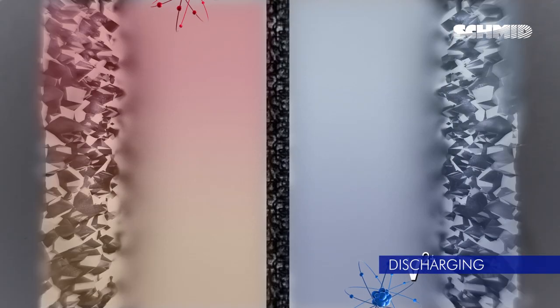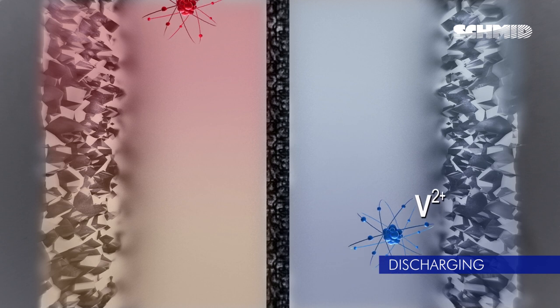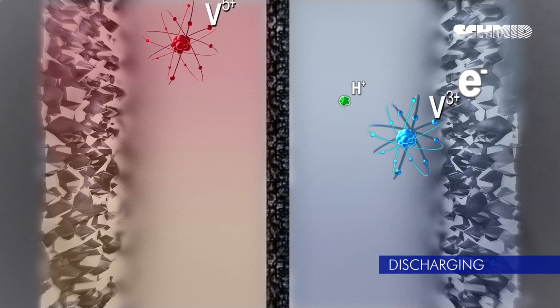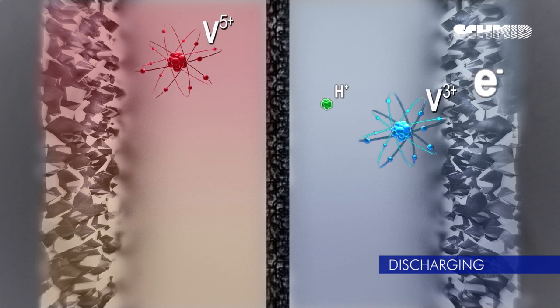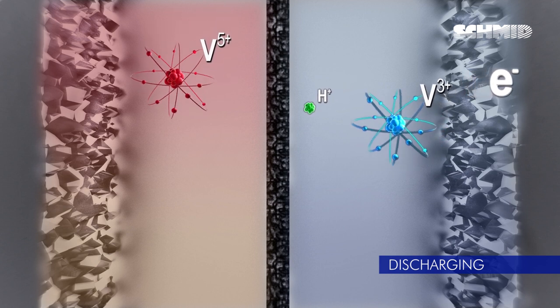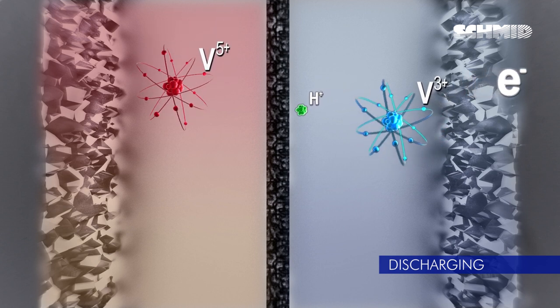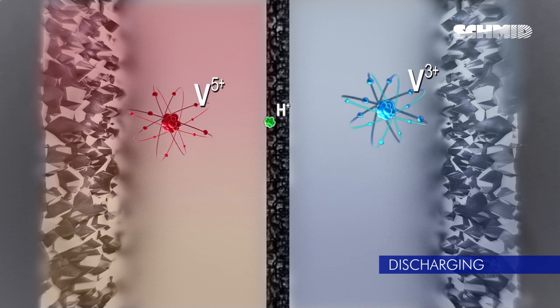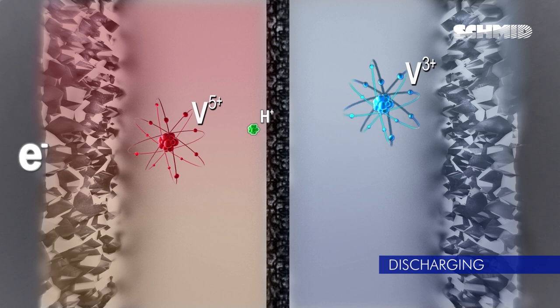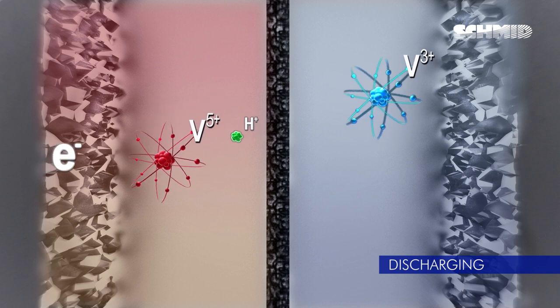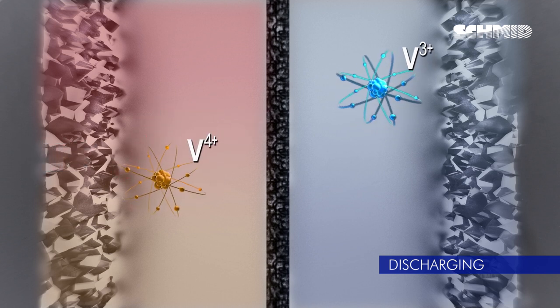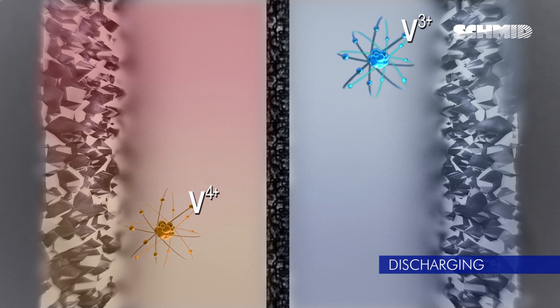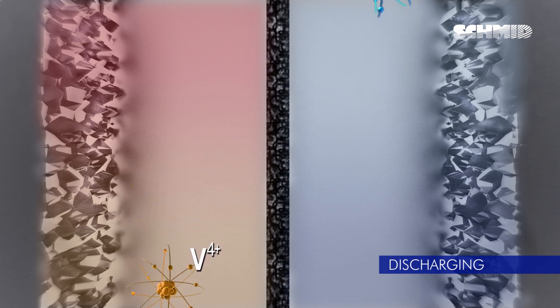At the molecular level, the reverse of the charging reaction occurs. Vanadium 2 is oxidized to form vanadium 3, releasing an electron which carries the electrical energy. For charge balancing, a hydronium ion crosses the ion conductive membrane. Vanadium 5 is reduced by an electron under consumption of a hydronium ion. The electrolytes leave the cell in their discharge states in the form of vanadium 3 and vanadium 4.